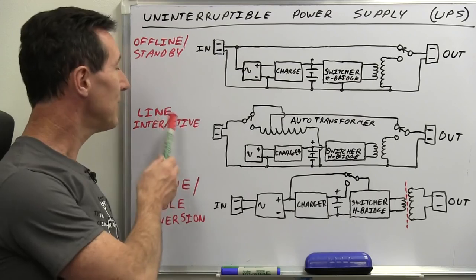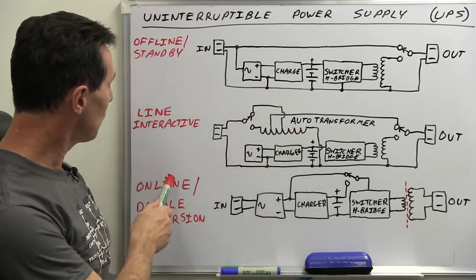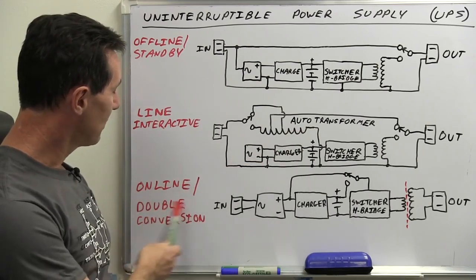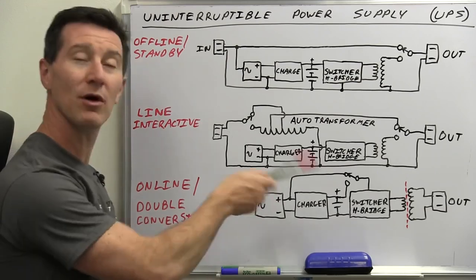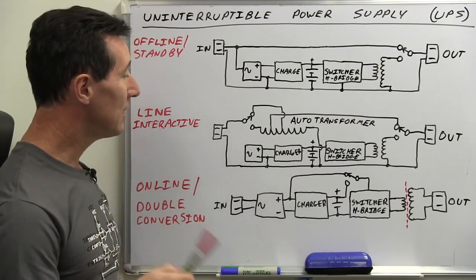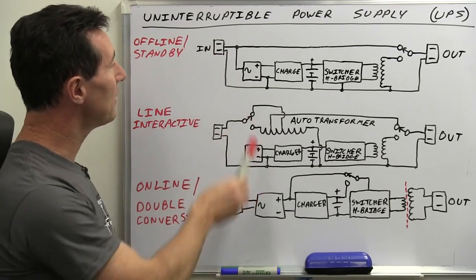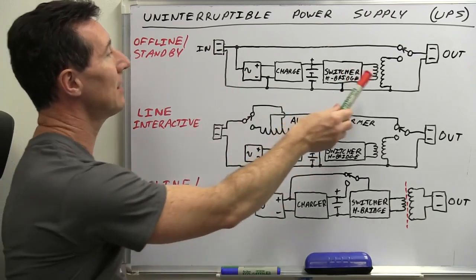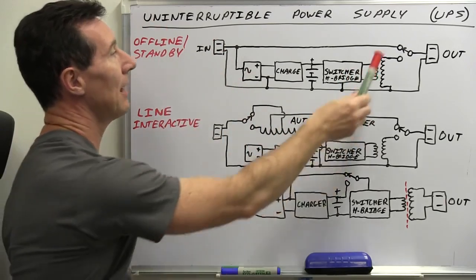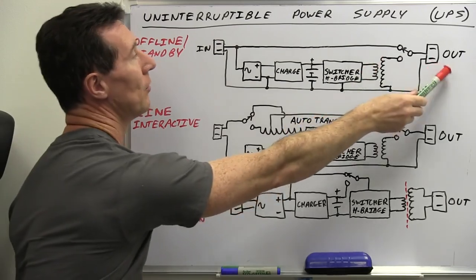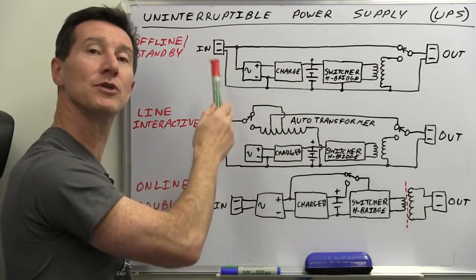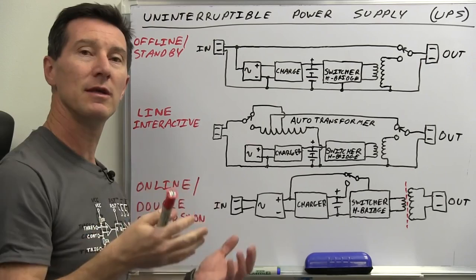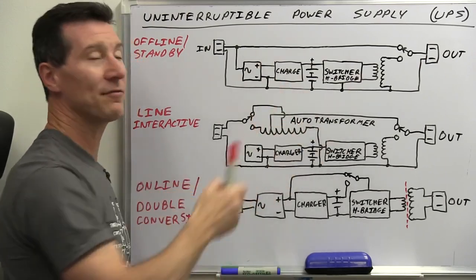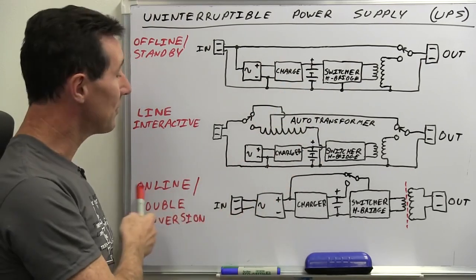Now I'll skip this line interactive one for a second, and jump straight down to the online, or double conversion, type. You'll see why it's called double conversion in a second. Now the difference between these two basic types is that the offline type, as I said, usually has the output powered directly from the input, switched straight through, so the battery backup part is offline.